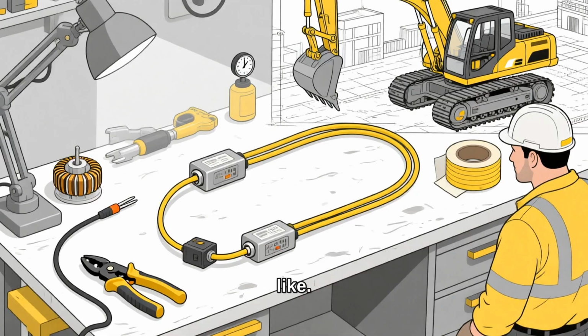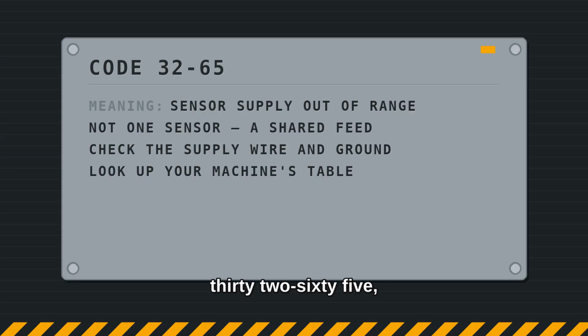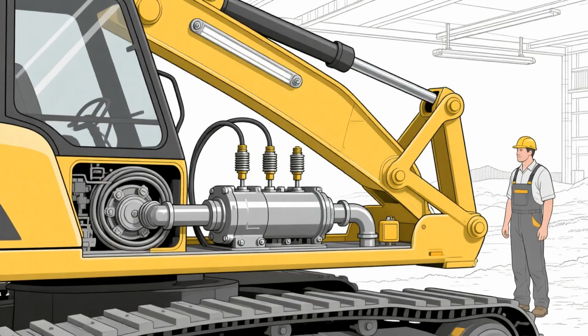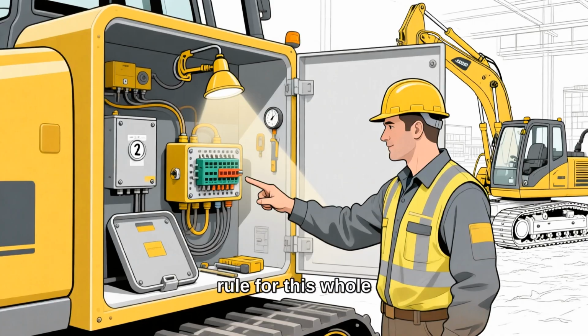Here's what that looks like. Say the display shows 3265, sensor supply voltage out of range. That isn't one sensor failing. That's the feed every sensor shares. Chase the one sensor that complained and you'll be there all afternoon. Which gives you the rule for this whole video: a code is an address, not a culprit.